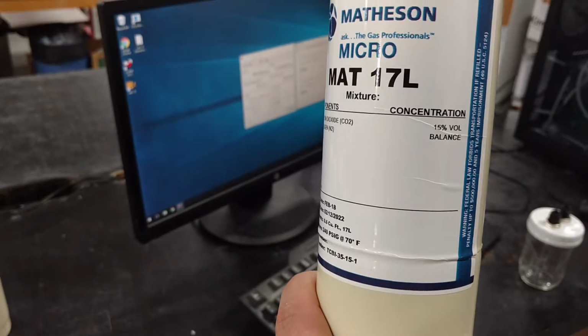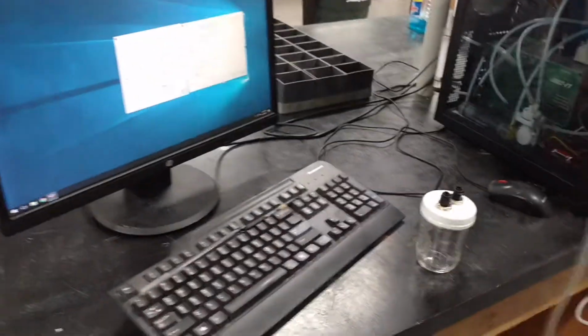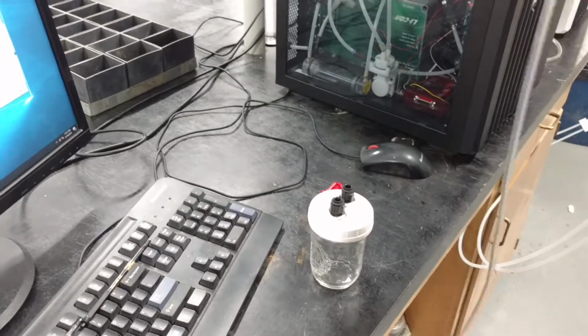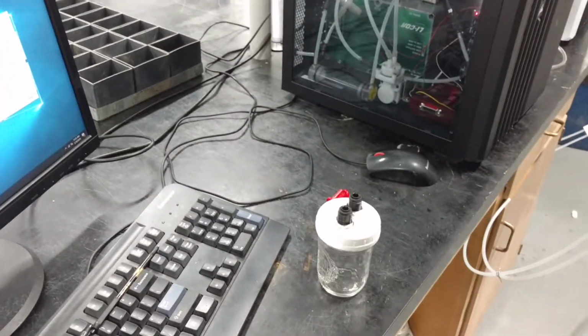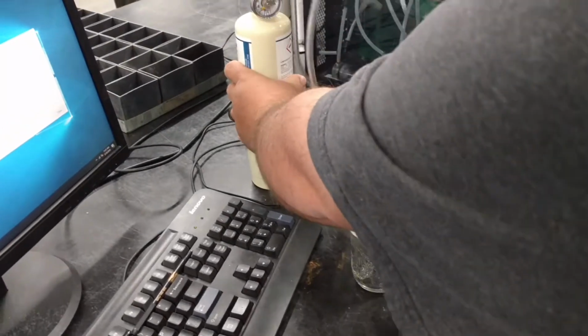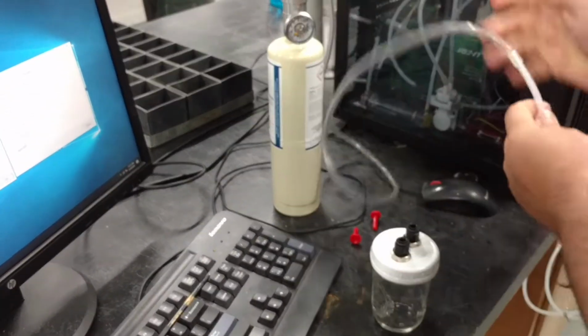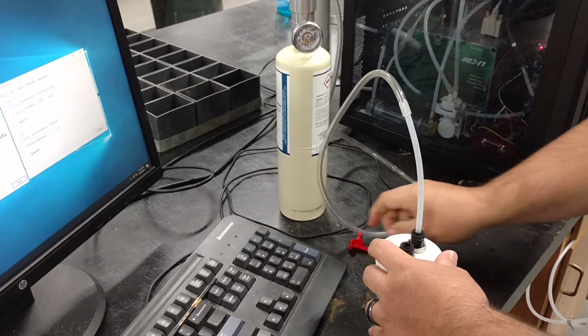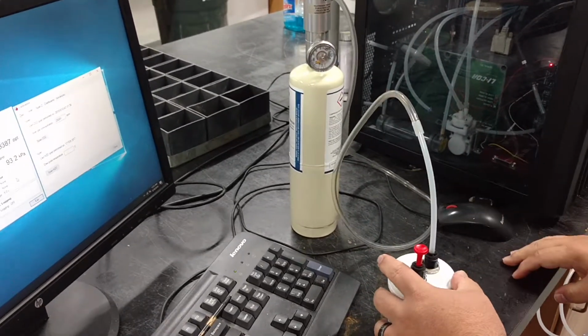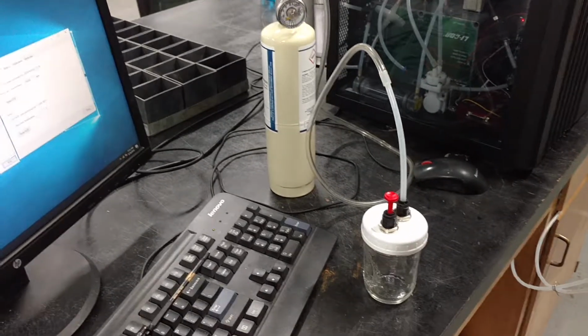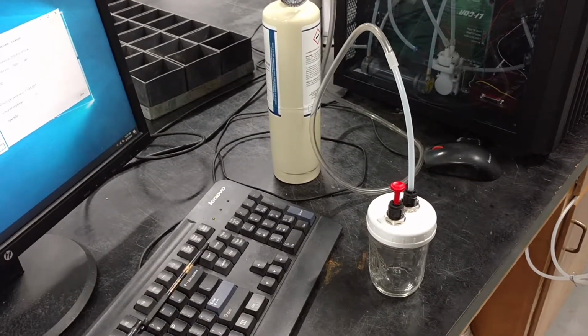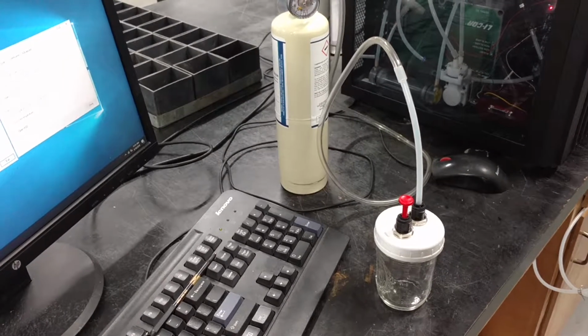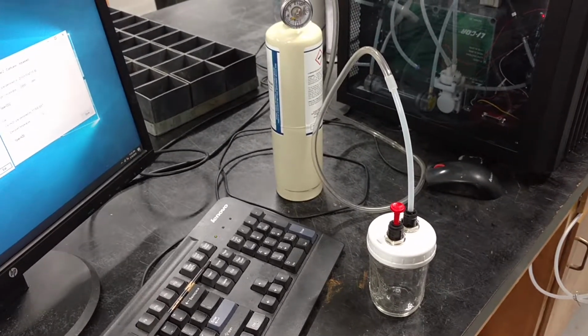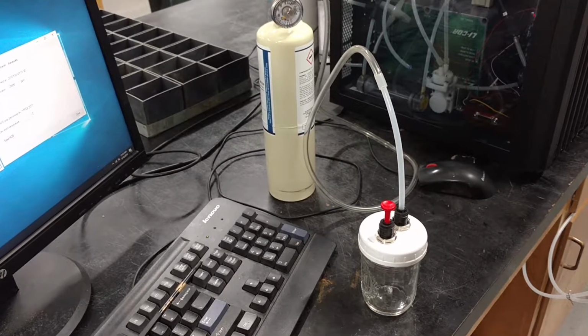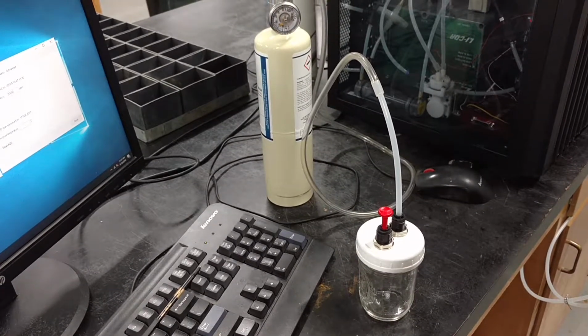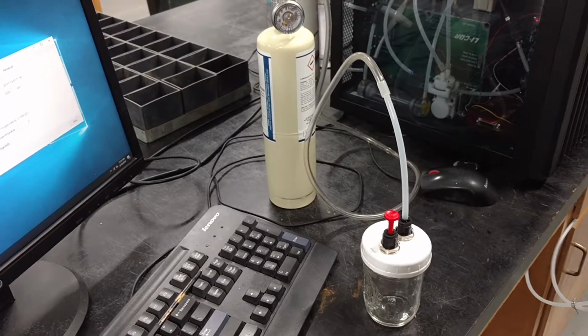The third calibration gas today is a 15% CO2 with a nitrogen matrix. Again, you're going to connect that canister to your regulator and set the flow rate at about 2 liters per minute before connecting to your jar. It's important to note that following calibration, you can check the accuracy of your calibration by using any of the calibration gases across your span. You follow the same procedure and you can look at the readout within your Licor software or within the CO2 Automation software itself. If these are not falling where they are expected, we recommend recalibrating.